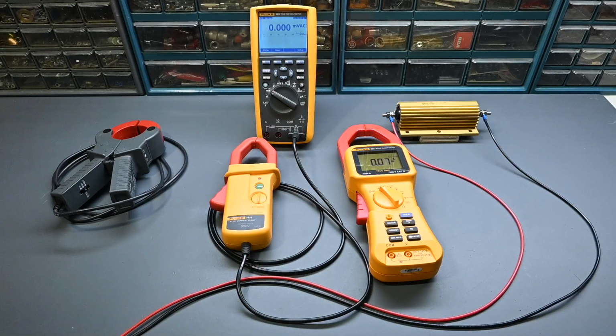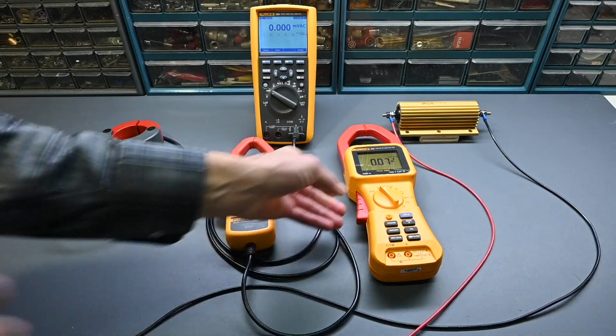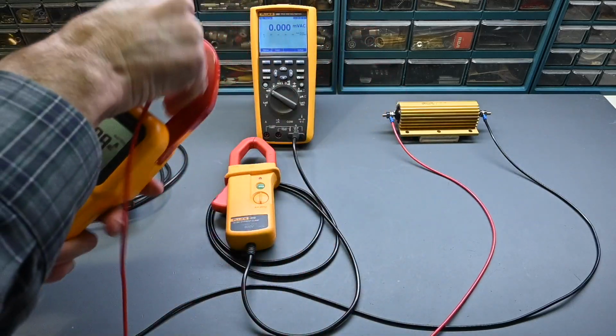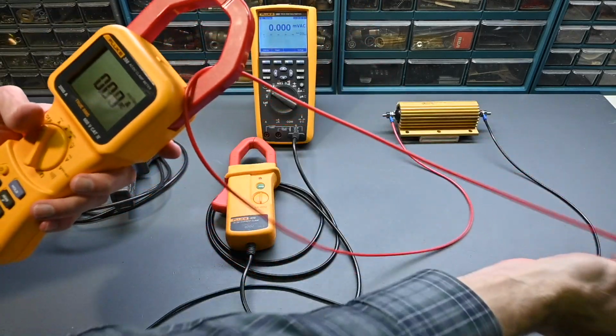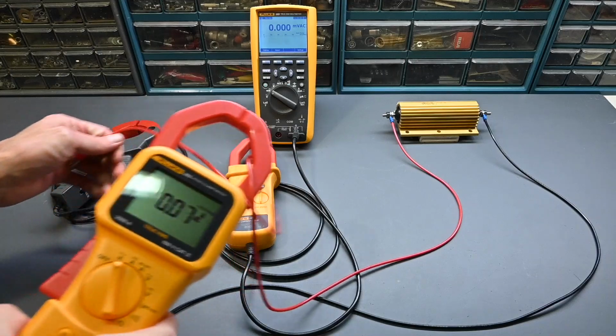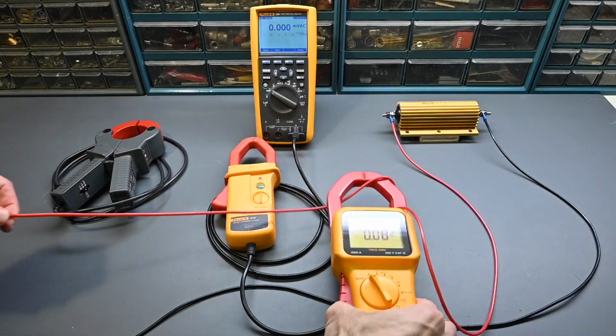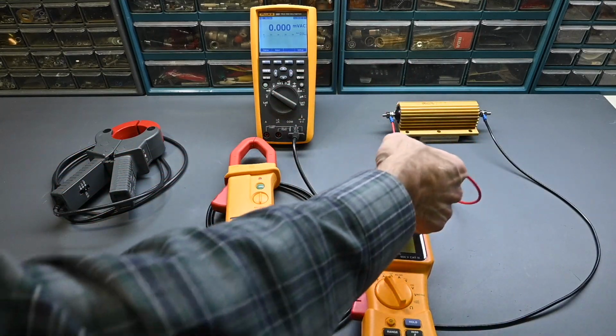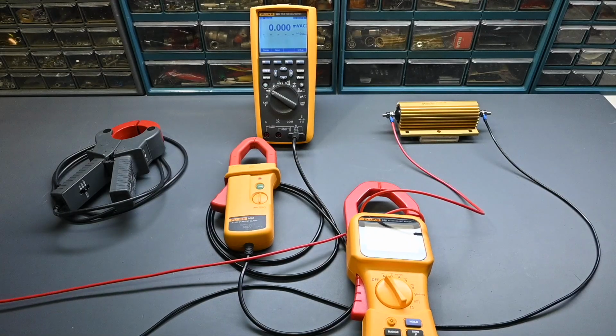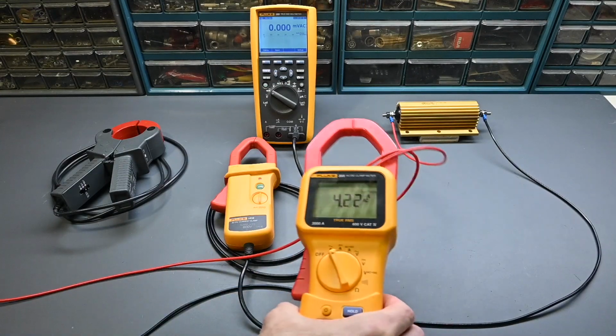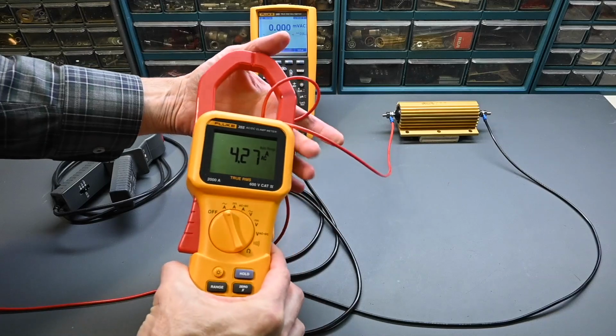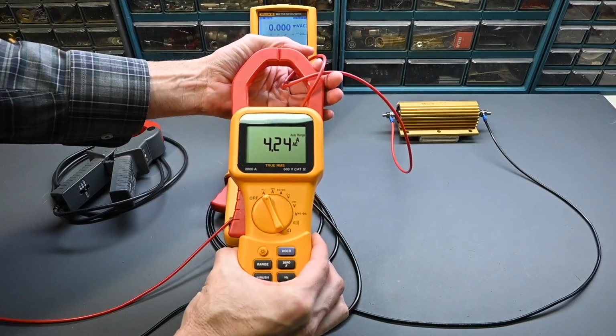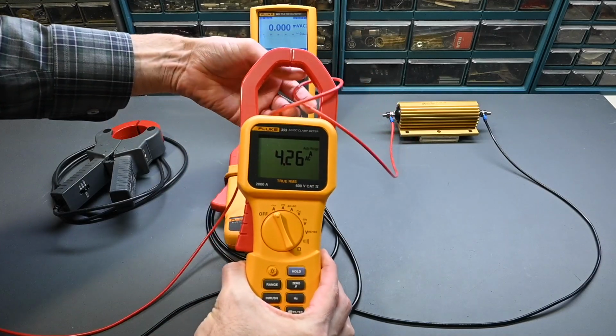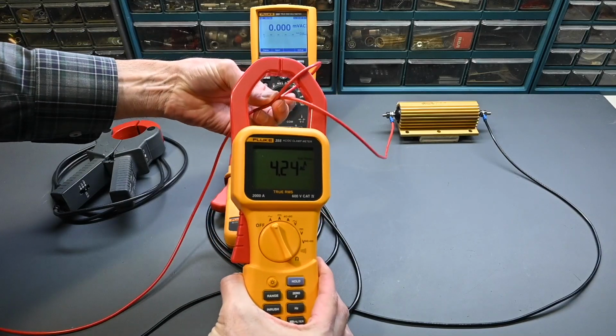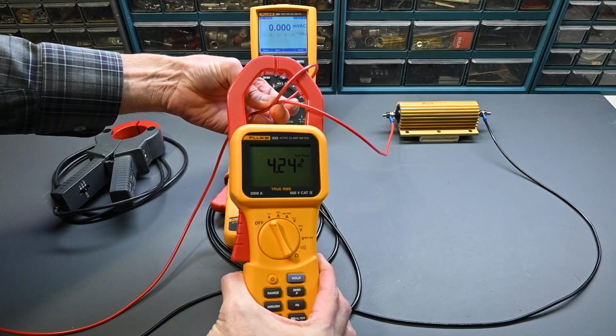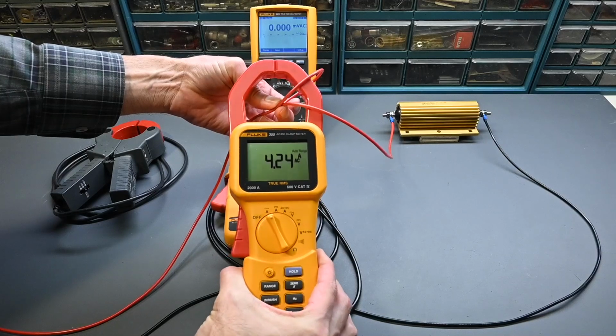So I'm going to disconnect this lead right here and go back to this clamp, and again just loop it through like so, and go back over and move this here just a little bit. Connection over here again. So actually I doubled it up right there, so now you can see it's reading 4 amps. It's passing through twice, so it was 2 amps, but when it passes through the current clamp jaws twice, it doubles the current reading.